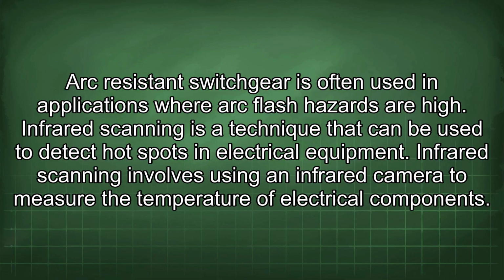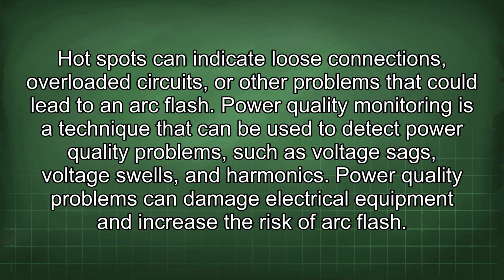Infrared scanning is a technique that can be used to detect hotspots in electrical equipment. Infrared scanning involves using an infrared camera to measure the temperature of electrical components. Hotspots can indicate loose connections, overloaded circuits, or other problems that could lead to an arc flash.